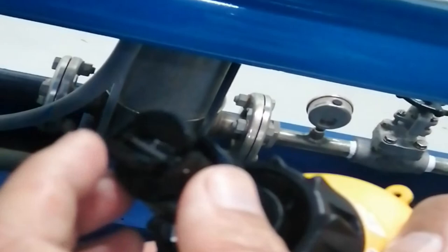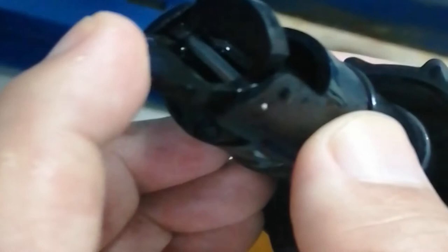As you can see, the paddle wheel was misaligned and cannot move freely. Paddle wheel is a magnetic type. The flow and the revolutions of the paddle wheel are proportional to each other, thus by spinning the paddle wheel with the force from the flowing fluid, it becomes possible to measure the rate of this flow.